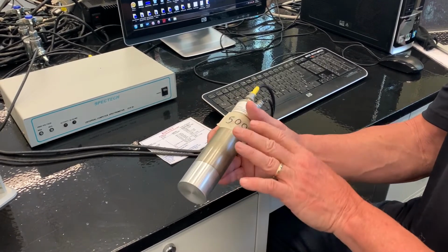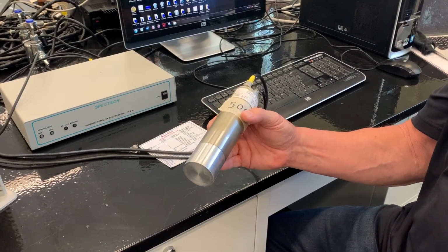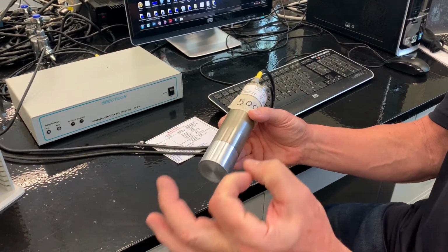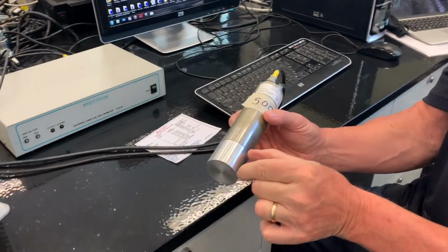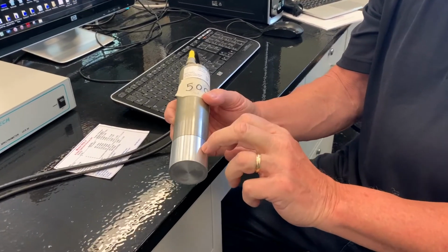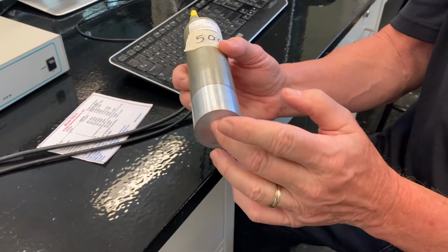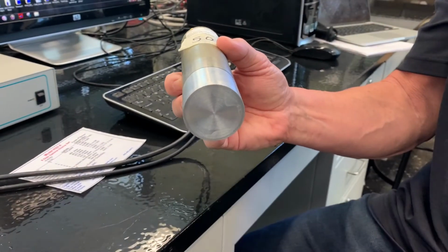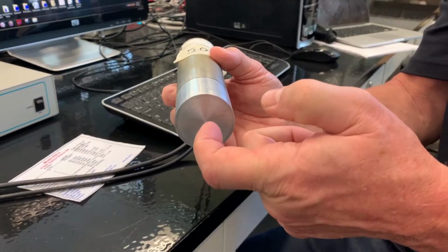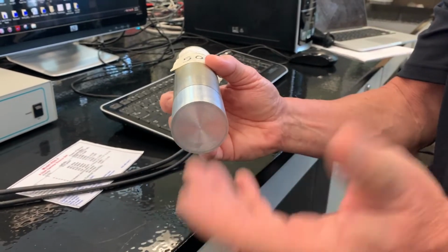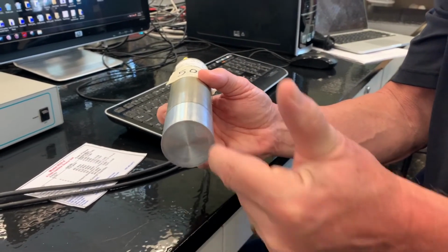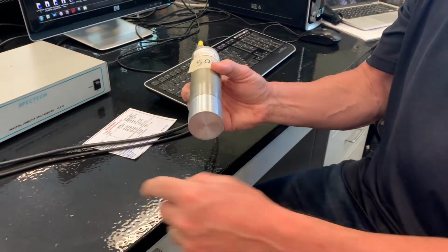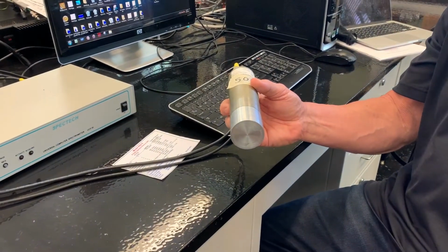So we've discussed this as a cartoon drawing, but this is physically what it looks like. The sodium iodide crystal is about that big and about that thick, and it's sitting right here. This aluminum shield, if you actually tap the front, you can tell it's much thinner than the side, and that's because we don't want the aluminum to absorb too many gamma rays that are coming in. And so we want this surface here to be a thinner aluminum.